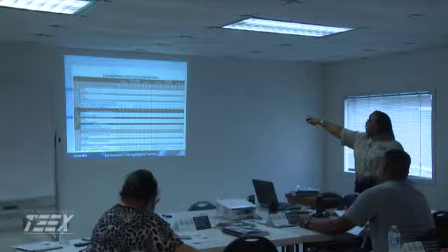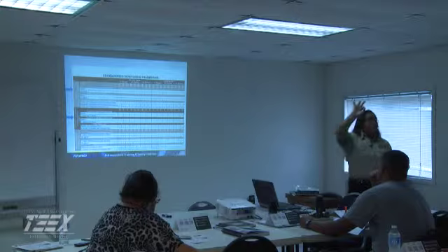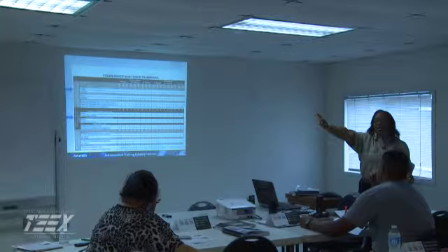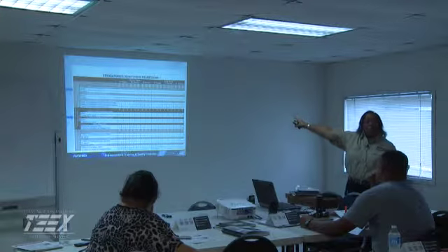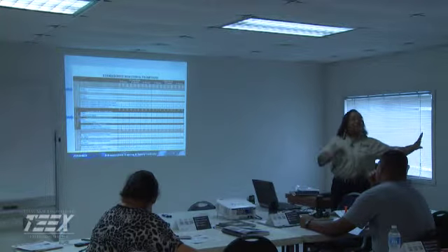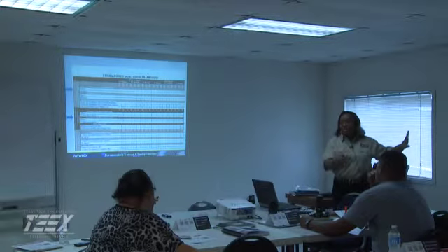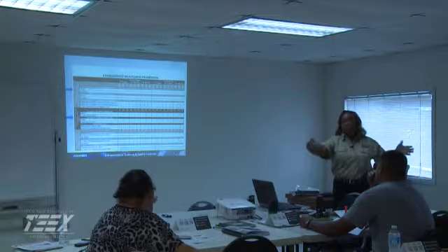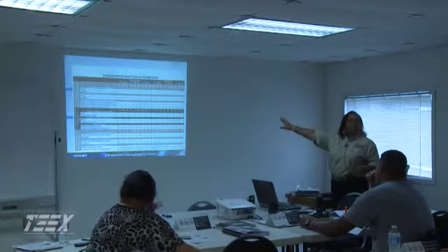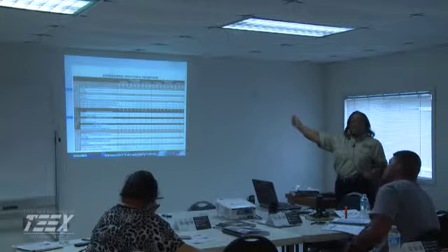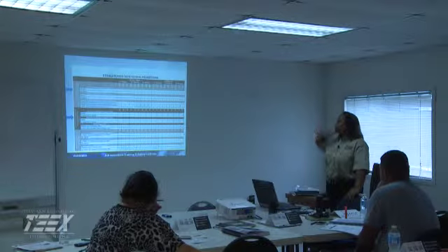No waiver, I'm doing it once every 3 years. Keep in mind, for groundwater, we're testing once every 3 years anyway. Okay? But with that waiver, I have an exceptional system. I don't have a problem with this. So I apply for a waiver or an exemption. They give me longer to do the analysis. Does that make sense? So once you understand the quick reference guides, you know right away how to use them. They become very beneficial to you.